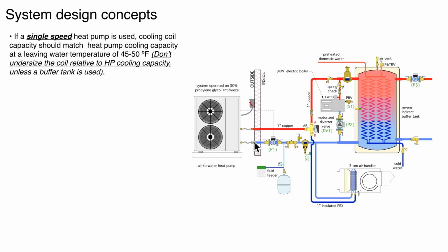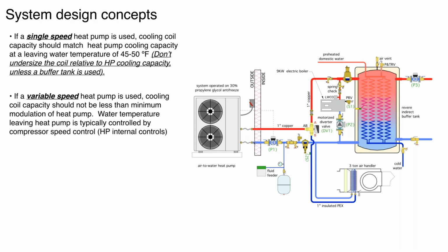Good news is many of the current generation air to water, as well as an increasing percentage of water to water heat pumps, are going to use inverter compressors, variable speed compressors. So when we do that, at least in my opinion, since the heat pump can control its capacity based on maintaining some set chilled water temperature, you don't need to go into the buffer tank to do cooling. So again, we're coming out to a diverter valve, and we're simply going down through our coil, coming back to our heat pump. When we switch over to either space heating, or even in the summer, maintaining some temperature in this tank, our diverter valve simply sends it up through, and I'm showing an electric boiler here as backup.